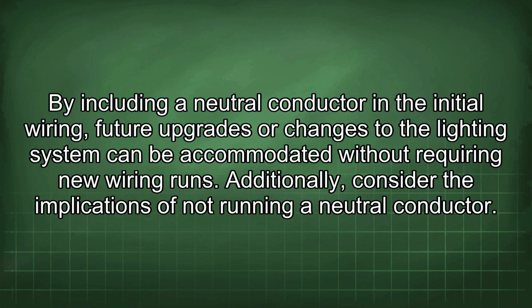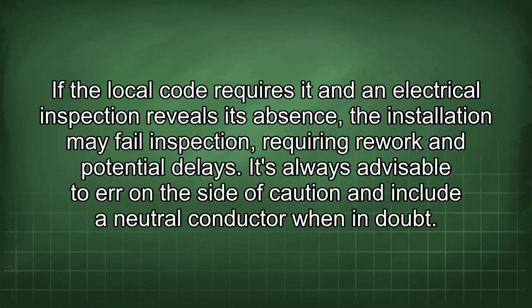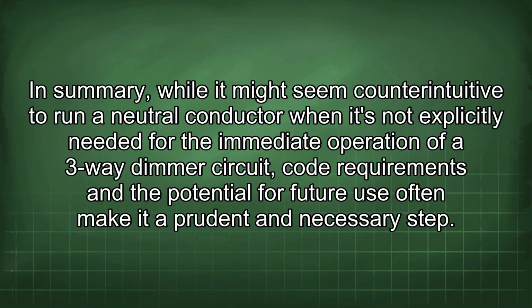Additionally, consider the implications of not running a neutral conductor. If the local code requires it and an electrical inspection reveals its absence, the installation may fail inspection, requiring rework and potential delays. It's always advisable to err on the side of caution and include a neutral conductor when in doubt.